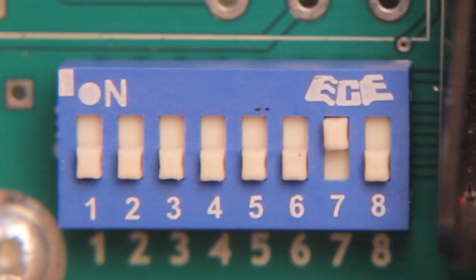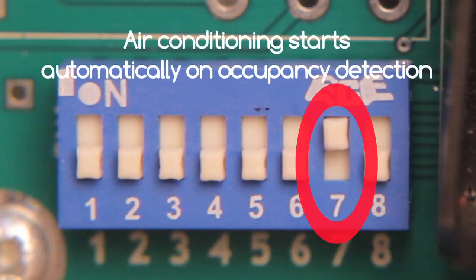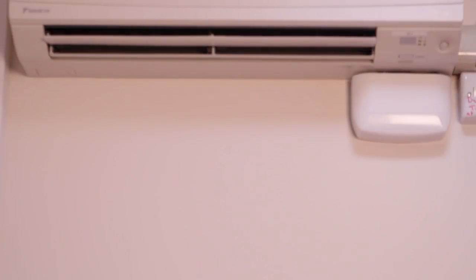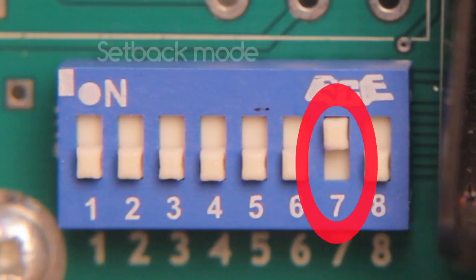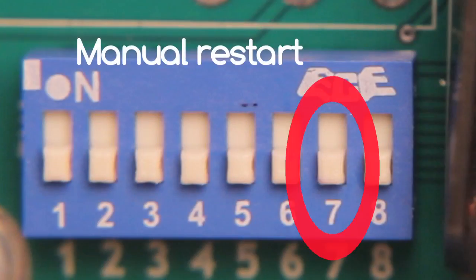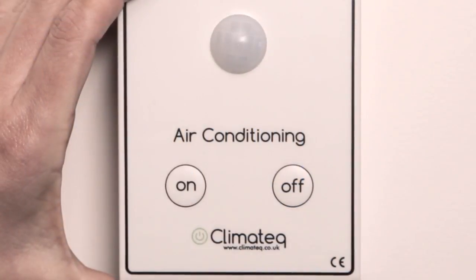Switch seven controls how you want the air conditioner to start when occupants return. In the on position, the air conditioner will start automatically when occupancy is sensed. This switch must be set on if you're using the setback mode or if you're mounting the control on the ceiling. In the off position, the air conditioner is manually turned on by the occupant using the button on the control, and it can also be manually turned off.